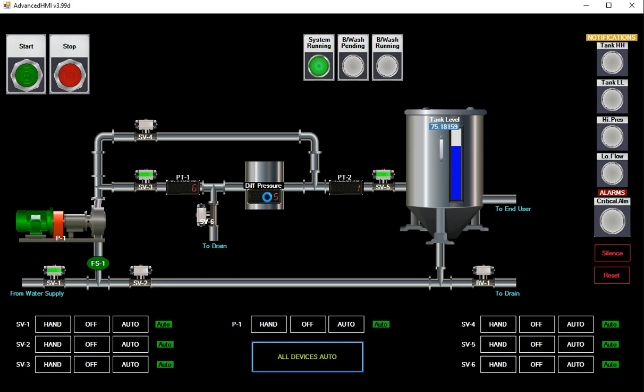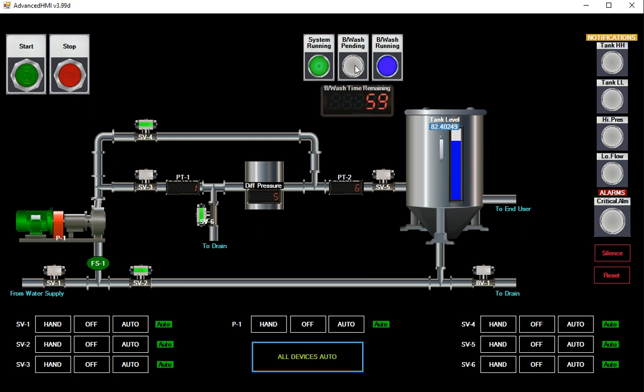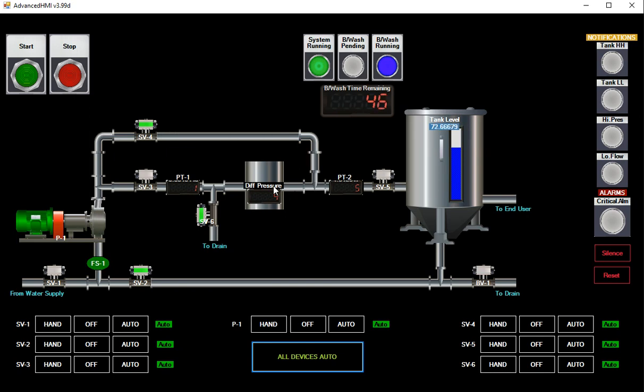Pressure reaches five so you have a backwash pending. And there you go, backwash pending. This closes, that closes, that closes, this one opens, that one opens, that one opens. It's pulling water from here up through the pump, here on the other side of the filter, and pushing it out to drain.